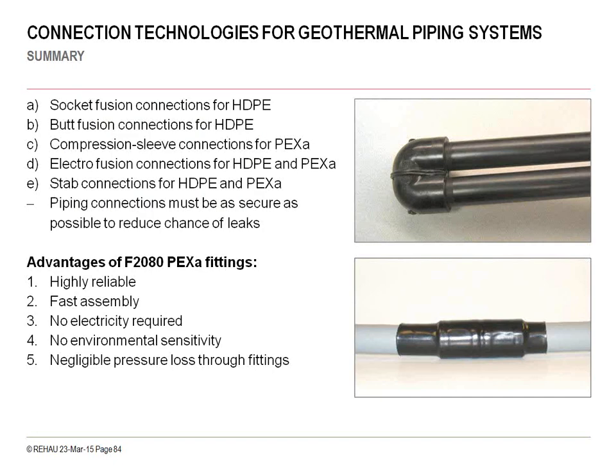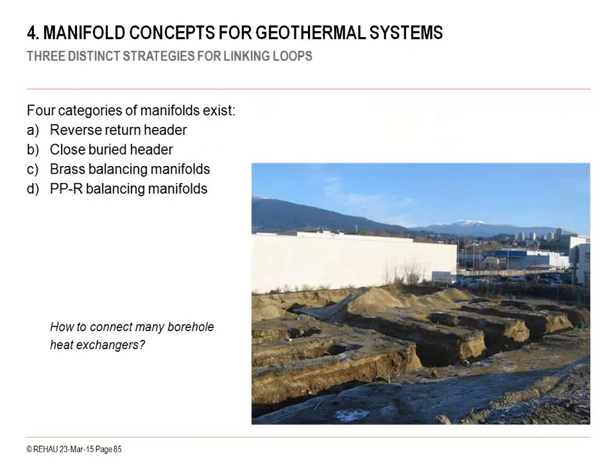With the heat fusion of the HDPE pipes, generally it's a two-man operation, and the skill set is higher because of the potential risk. I'm going to talk now about the manifolding strategies for PEX-A pipe material and HDPE that's typically done in the market. Talk about a reverse return in closed buried headers versus balancing manifolds.